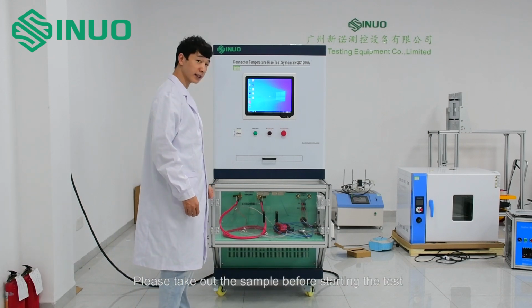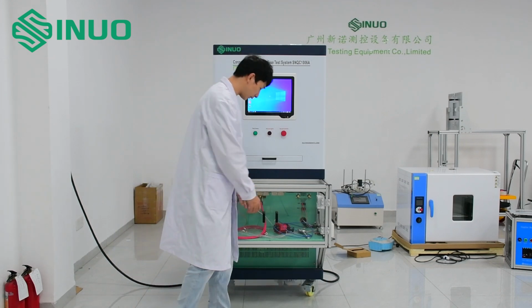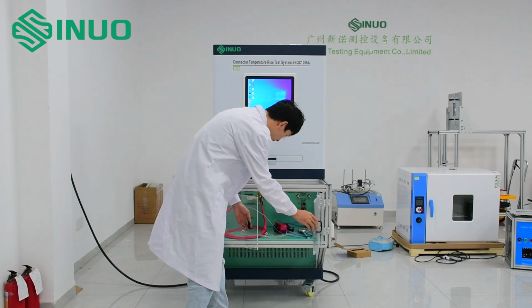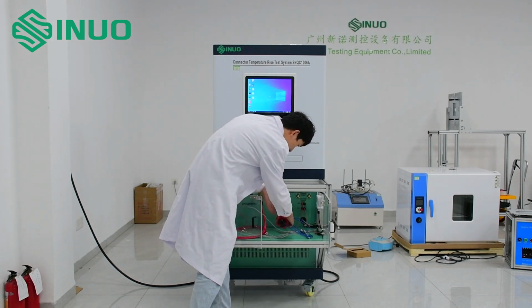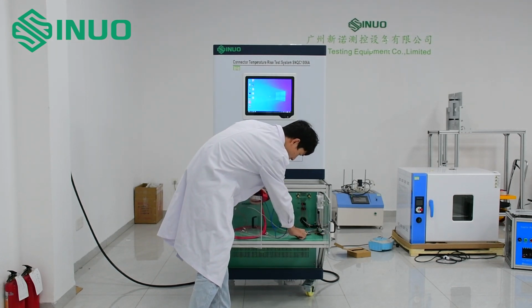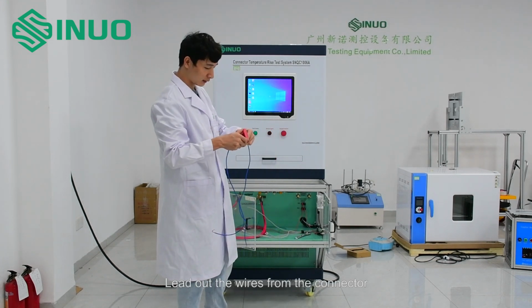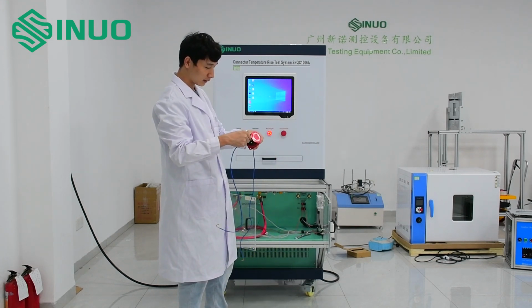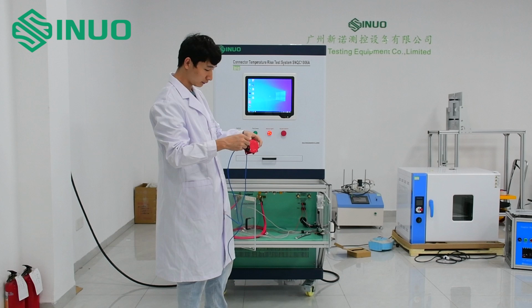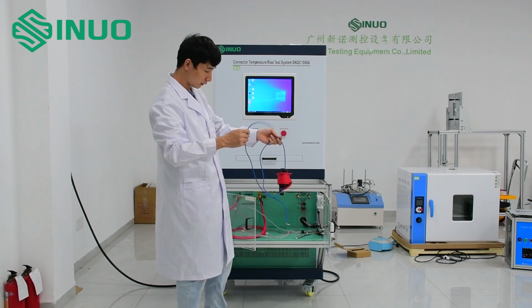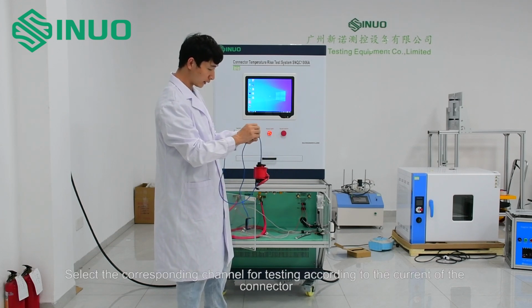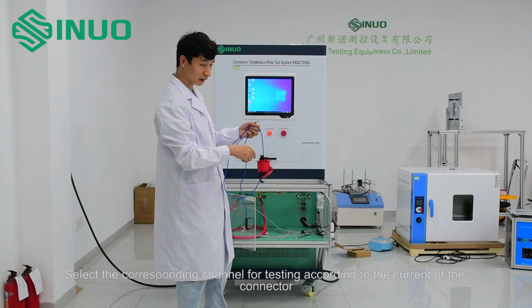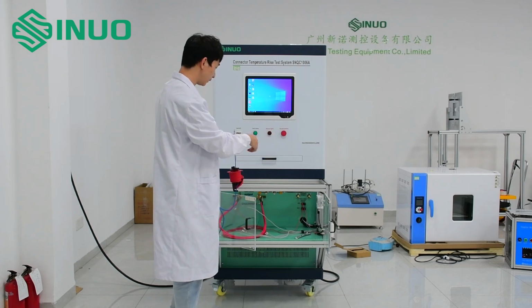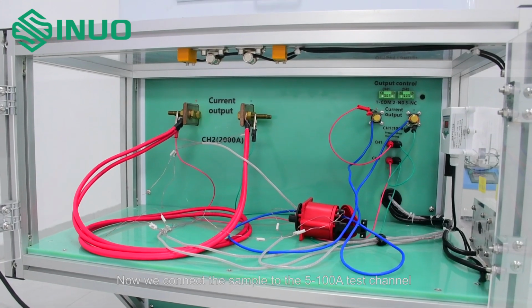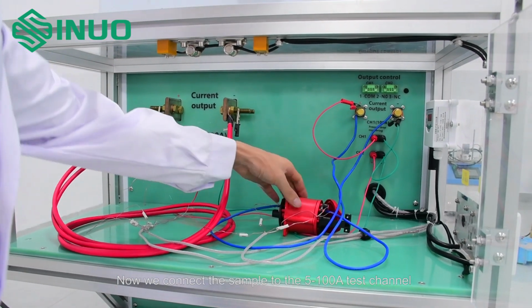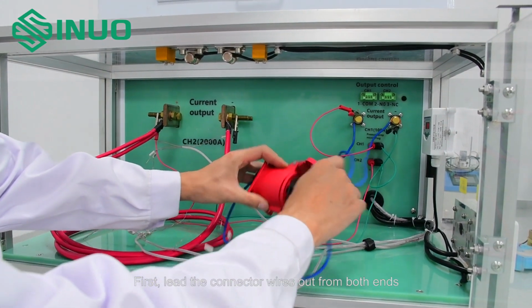Please take out the sample before starting the test. Lead out the wires from the connector. Select the corresponding channel for testing according to the current of the connector. Now we connect the sample to the 5 to 100 A test channel.